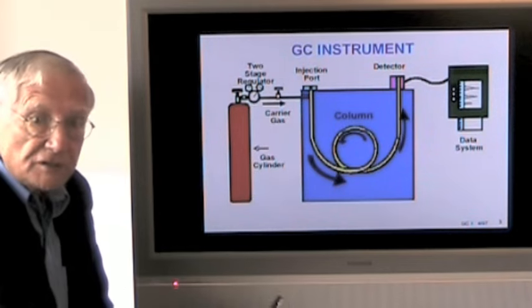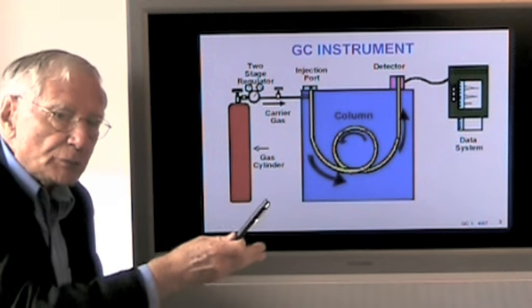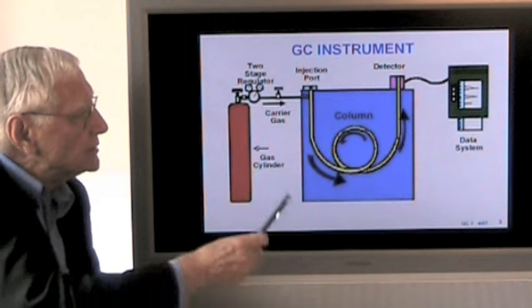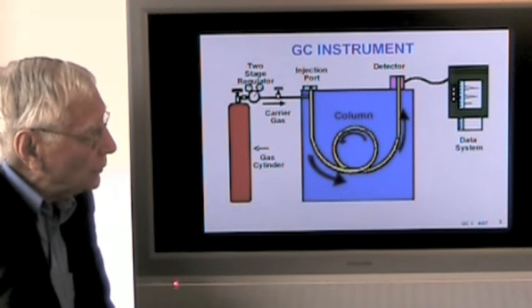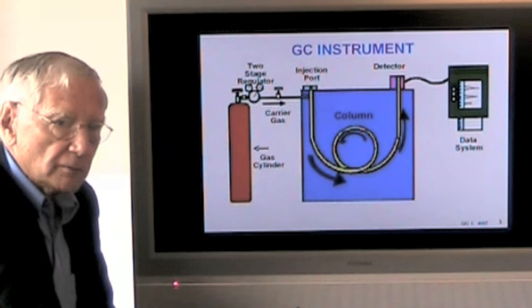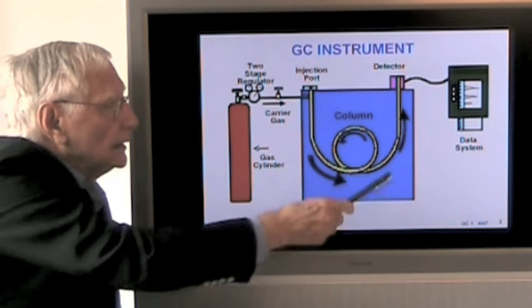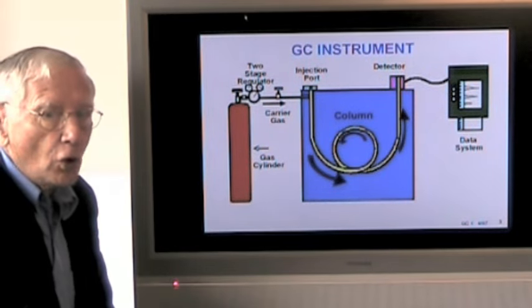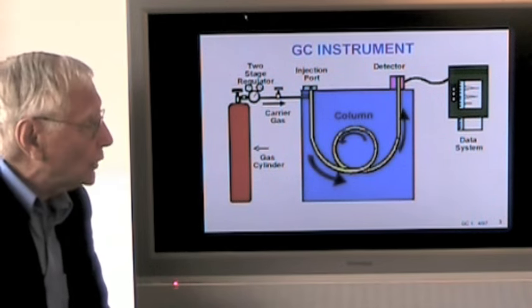This injection port is heated. It is used to rapidly vaporize any sample which happens to be a liquid or solid at room temperature. Once vaporized, the carrier gas carries it into the column where the separation occurs. After the column, the sample components enter a detector where an electrical signal is generated. That signal is proportional to the concentration of the sample. And that signal is recorded here on the data system. In today's world, this is almost always a computer. Earlier times, we've used integrators, and much earlier times, even a very simple recorder.